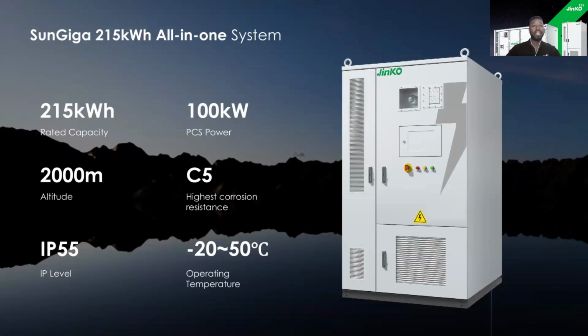It's able to operate at altitudes of 2,000 meters. It can have an optional corrosion resistance up to C5 rating. Externally rated, the enclosure itself, the cabinet, is IP55 rated, but internally the batteries themselves are IP67 rated. And yeah, the operating temperature is able to operate from -20 to +50 degrees Celsius, so centigrade. So it's able to operate right across the majority of environmental conditions that you might expect to come across within Europe. Can go to the next slide, please.